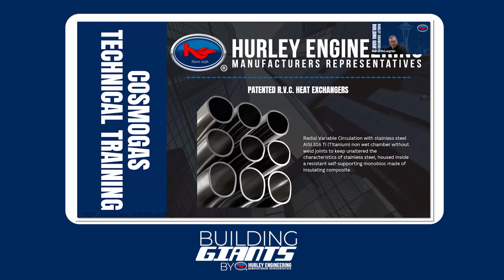It's still a water tube design. It's a radial variable circulation, so they've got a different shape than what you would typically see. It's not quite as oblong. It doesn't tend to foul as much. It doesn't have flow issues. It keeps the turbulence where they want to keep the turbulence. And it's constructed of 316 titanium stabilized stainless, so really good corrosion resistance properties and excellent against thermal stresses as well. Another thing they've done is they've ensured that there's no weld joints anywhere in the wetted surfaces. Every weld joint you have is another potential for failure, another potential for problems, and that's been eliminated by having a complete seamless heat exchanger.